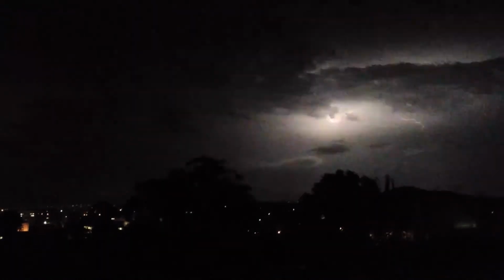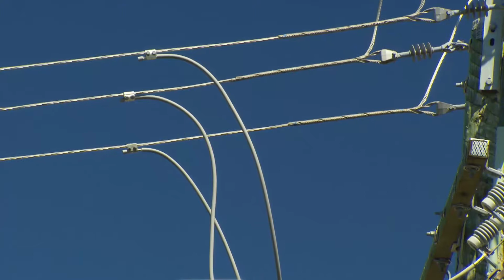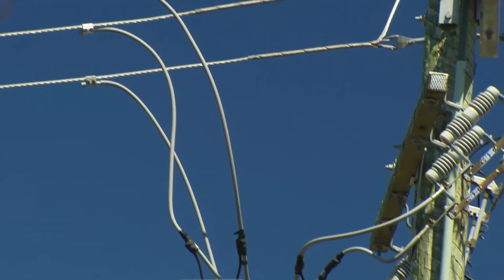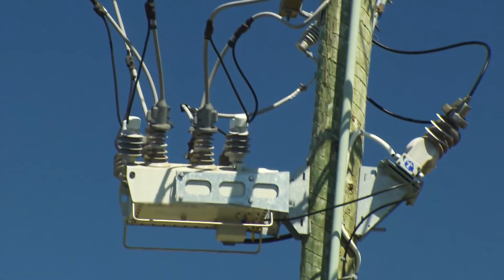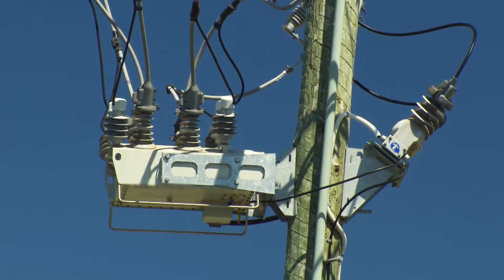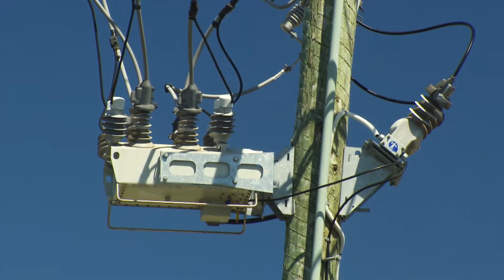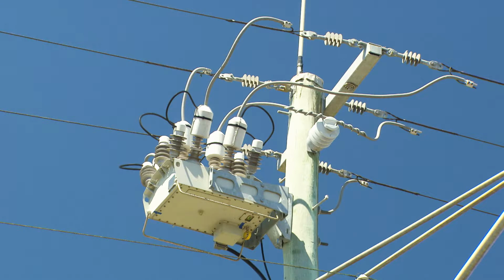Lightning strikes in power lines are common. They can generate large impulses, which travel along the conductors. Surge arresters should be fitted to both sides of the recloser to protect against impulses from either direction when in the closed or open position. Surge arresters can be bolted directly to the tank, so the surge current is diverted to the ground through the tank. No separate earthing is required in this case.